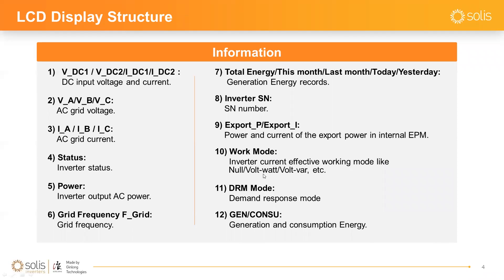Export P and Export I show the power and current you're exporting to the grid — these only appear when you've connected a meter or CT and enabled the internal EPM function. Work Mode is related to the grid standard code; some standards enable working modes like Volt-Watt or Volt-VAR, but most will show 'Norm.' DRM (Demand Response Mode) is mainly for Australia. The generation and consumption display is available after connecting a smart meter, and you can also see that data in the Solis monitoring system.